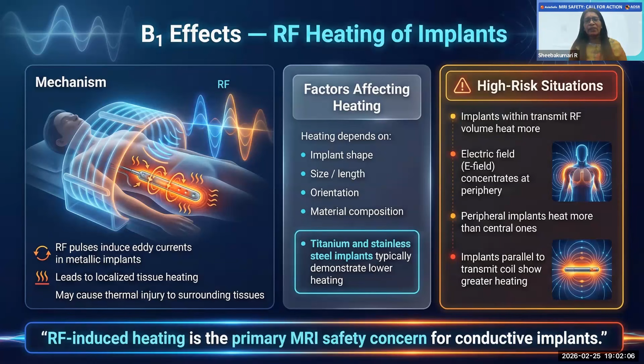In the same way, implants located peripherally heat more than implants located centrally. Also, an implant which runs parallel to the RF coil will experience more coupling and RF heating than a perpendicularly oriented implant. The RF heating also depends upon tissue perfusion, implant location, and also the age. If an area has good perfusion, for example the vascular implants and the implants placed inside the heart, there is a blood cooling effect, so these devices heat less. Also, embedded implants have the protection of heat dissipation by the tissue, so embedded implants heat less than externally fixed devices.